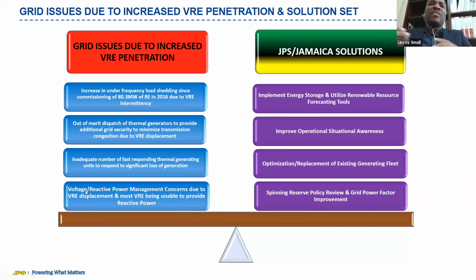So as a result, when you have a day of 40% renewables, that's 40% of generation providing real power but not reactive power, which the traditional thermal or firm units were able to provide. Because of that absence of reactive power support, it resulted in low voltages being experienced on the grid.